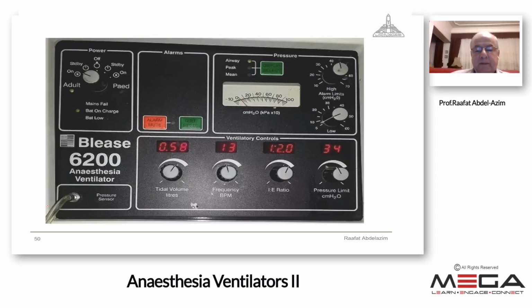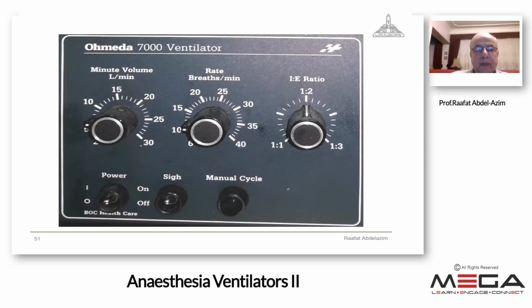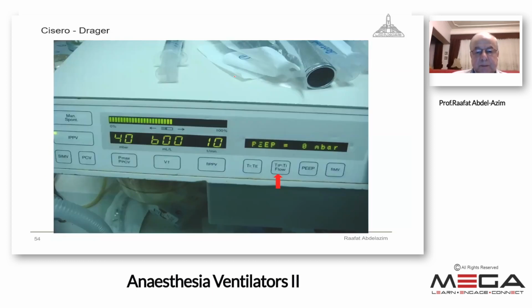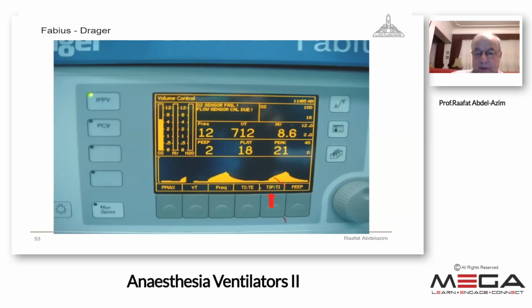Some ventilators have the parameters of tidal volume, frequency, and IE ratio, and in other ventilators the tidal volume is not there, but we can divide the minute volume by the rate to get the tidal volume. There is something called inspiratory pause to inspiratory time ratio, because I said before that there is a part of the inspiratory time called inspiratory pause, in which the ventilator stops its flow. Sometimes it is not there, or it is there and I can adjust its duration. So the duration will be displayed here as a fraction of the total inspiratory time.